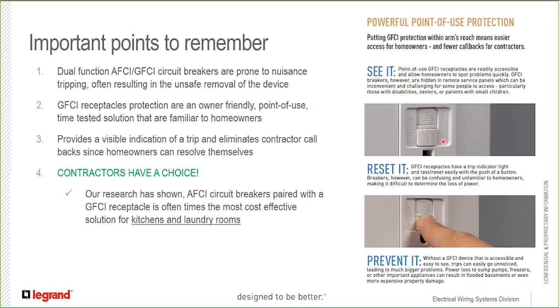Another important point to remember, a visible indication of the trip will eliminate contractor callbacks since homeowners can usually resolve these themselves. Ultimately, contractors have a choice, but as I've mentioned and as I'll summarize here, our research has shown that AFCI circuit breakers paired with a GFCI receptacle is oftentimes the most cost-effective solution for meeting new code in kitchens and laundry rooms.